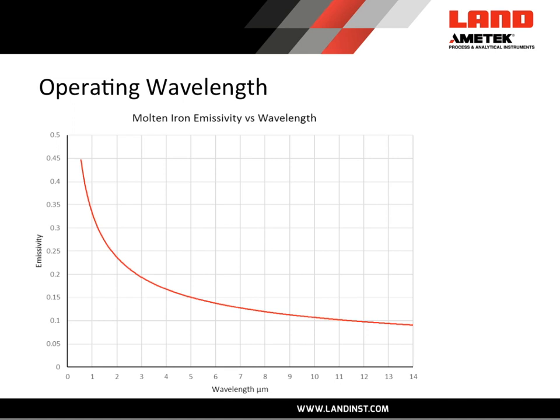If you go even further, out of the infrared into the visible part of the spectrum to a shorter wavelength of around 0.55 micrometers, the emissivity value has risen to 0.45 — a huge gain over 0.35 at just one micrometer. A pyrometer designer measuring temperatures for molten iron would tend to use very short wavelength detectors, operating short of the infrared and into the visible part of the spectrum.